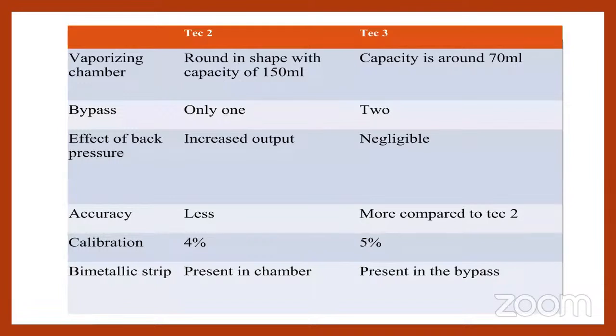The vaporizing chamber is round in shape, which has a capacity of 150 milliliters. In Tech 3, the capacity will be around 70. Only one bypass is available in the Tech 2 vaporizer. In Tech 3, two bypass chambers are available. And the effect of back pressure, that is basically the pumping effect and pressurizing effect, will be increased in the Tech 2 vaporizer, and very negligible in the Tech 3 vaporizer. The accuracy in Tech 2 is a little bit low when compared to the accuracy of Tech 3 vaporizers. The calibration is up to 4% of MAC, and in Tech 3, the calibration is up to 5% of MAC.